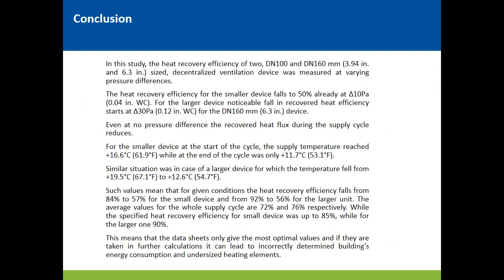And what are the consequences? The consequences can be that people will turn off this device because the incoming air will be colder than they expect. They do not want this cold draft, because actually sitting by this device while it was operating during these measurements, I also got cold just from sitting near it. Also, some heating devices could be undersized.